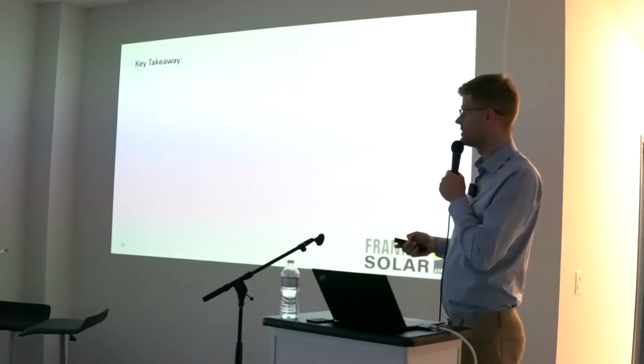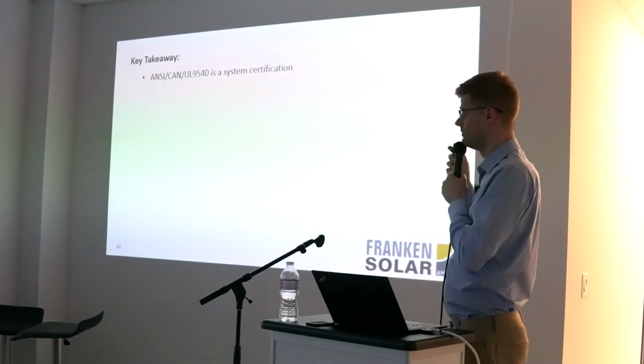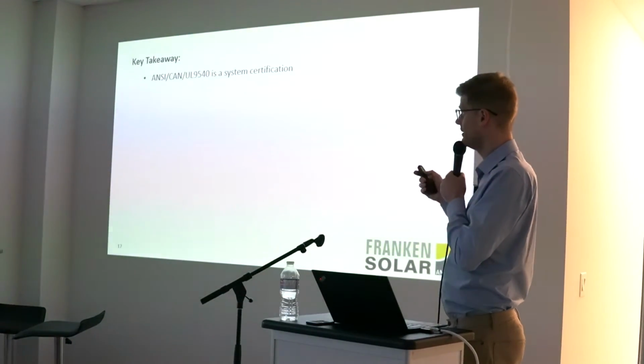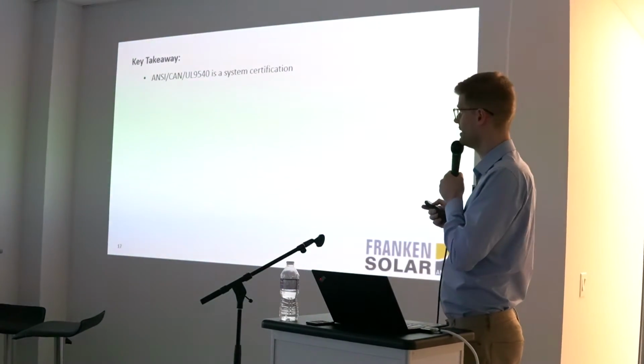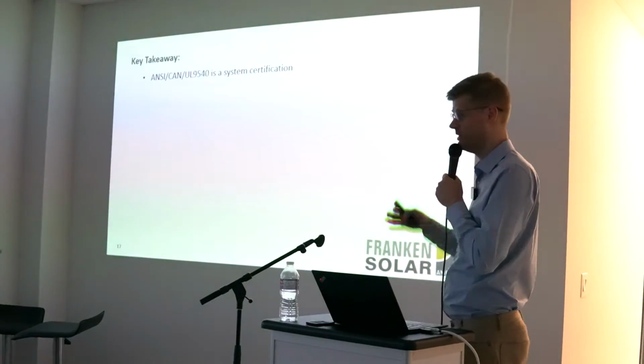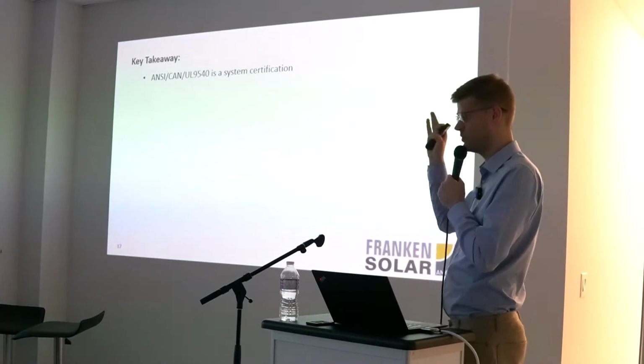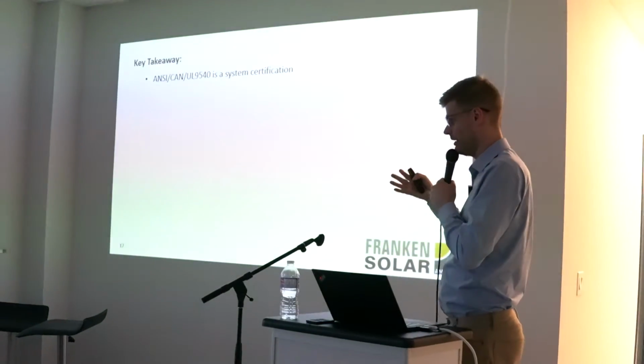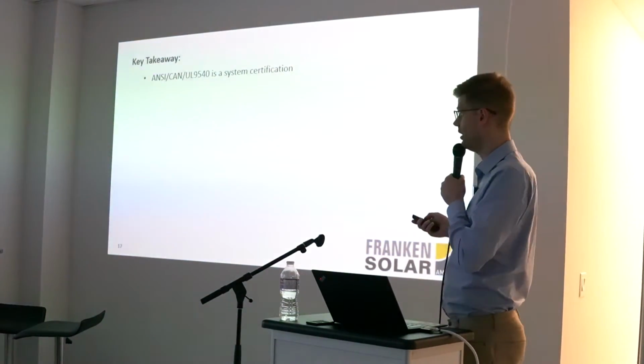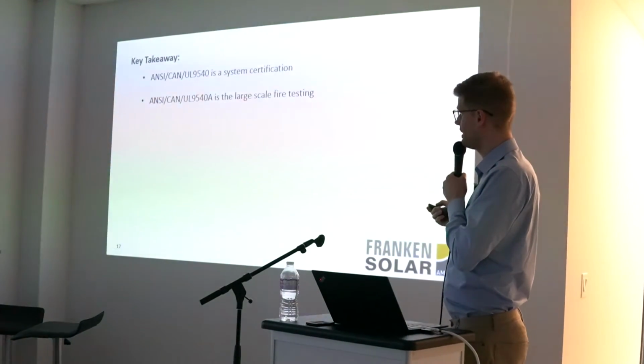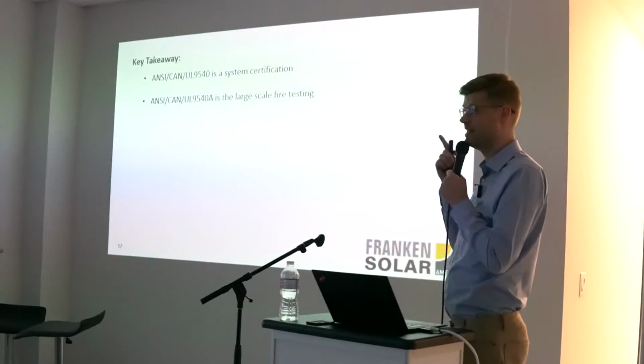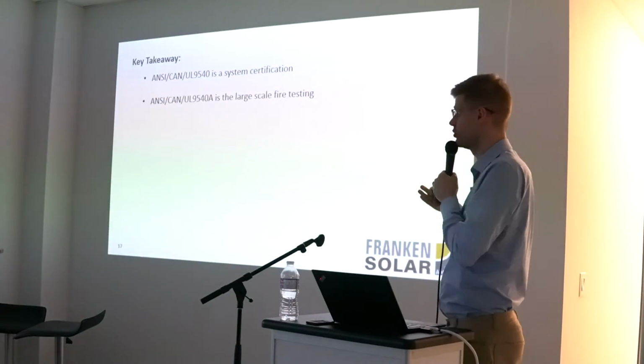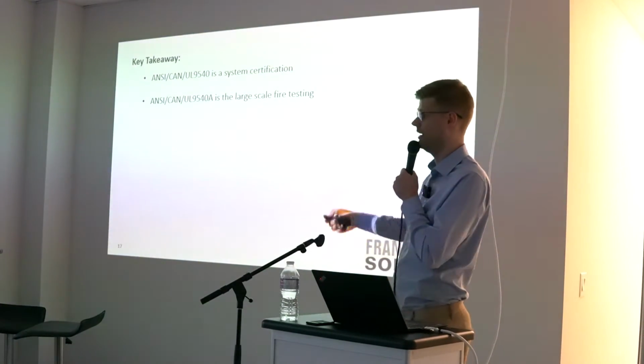Key takeaway to summarize that: UL9540, including the Canadian part, is a system certification. So inverter, battery, cabinet, transfer switch, whatever you or the manufacturer want to cover under that, is in one document. The 9540A is not a certification, it's a test that provides the values to the certification under 9540.